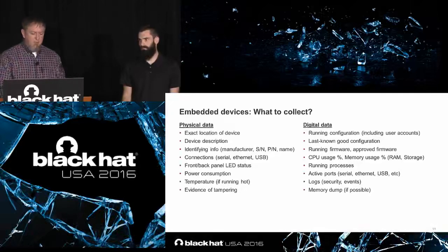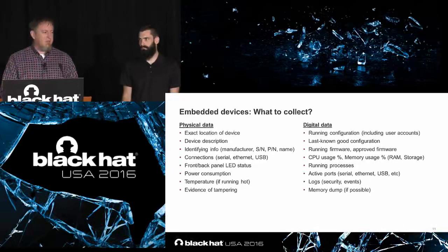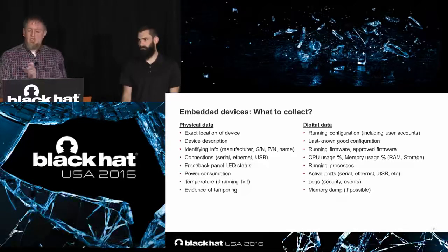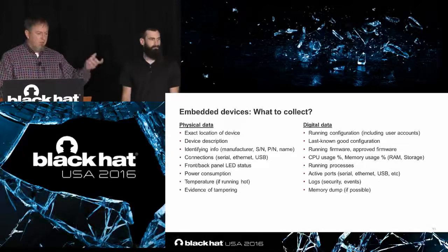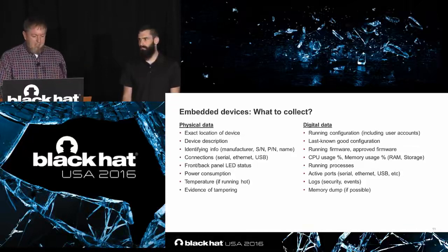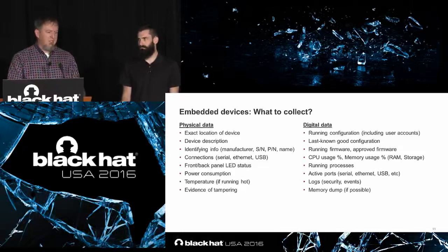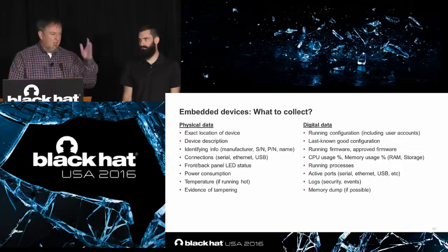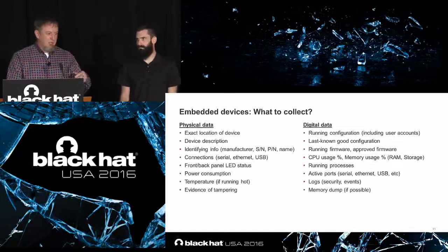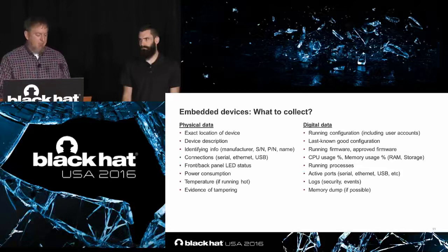So for embedded devices, what do we collect? I'm going to break this down into two items. We have physical data and then digital data. Physical data is like the exact location of the device, which substation or what platform out in the Gulf of Mexico, you've got an old platform, or what breaker cabinet it might be in, device description, serial number, part number. What are the LEDs? Whenever I got a call and there was a problem in a substation, send the technician out and say, well, what do the lights say on the front? Are they red and blinking, or are they all green and acting normal? See what the power consumption is, temperature.